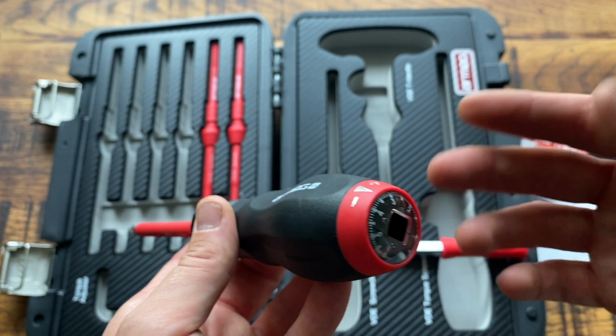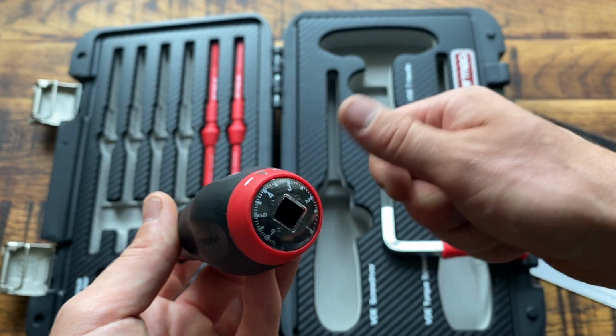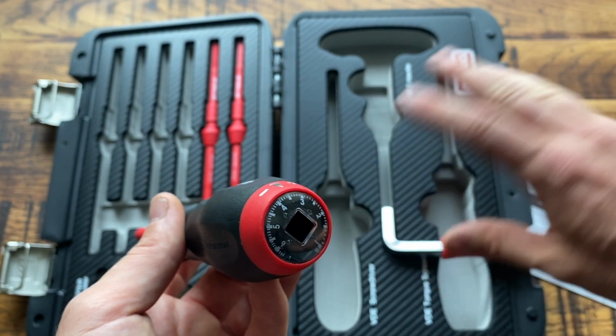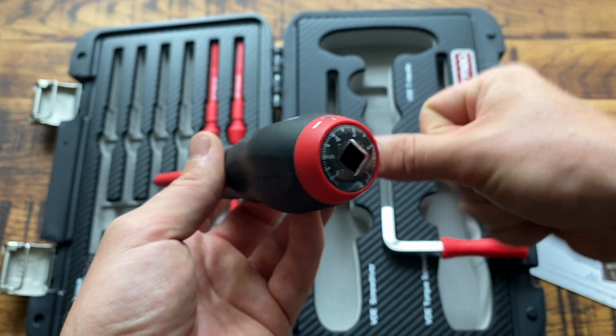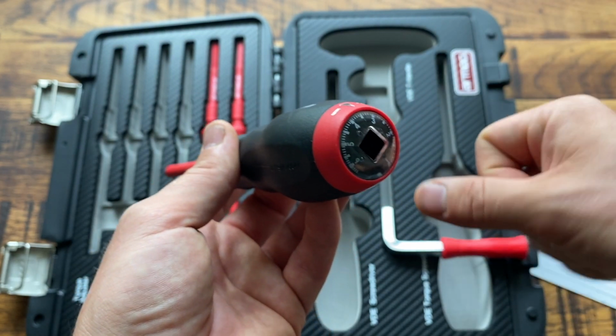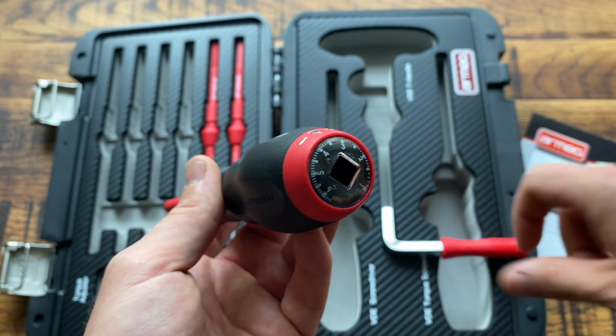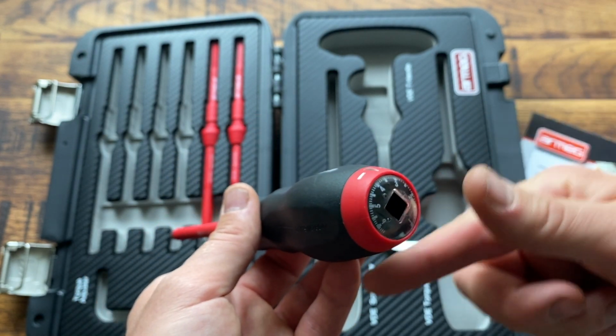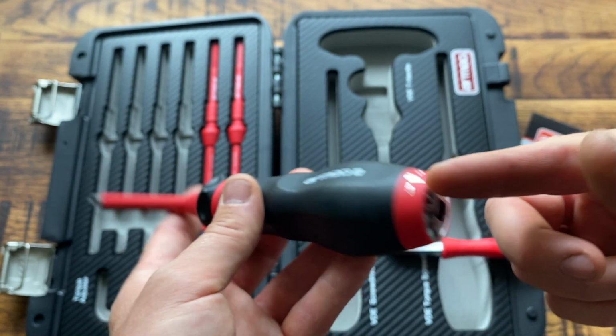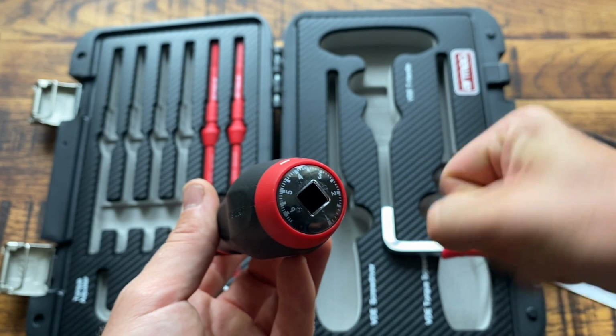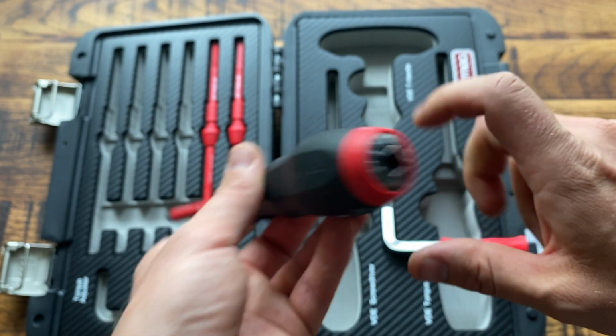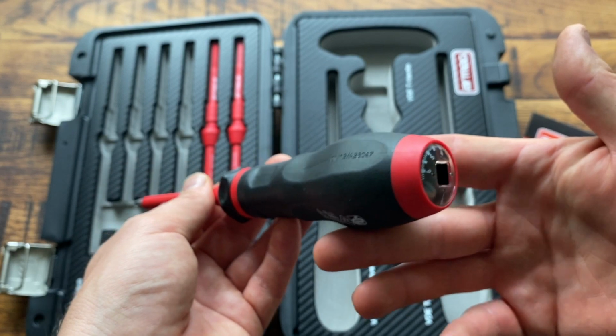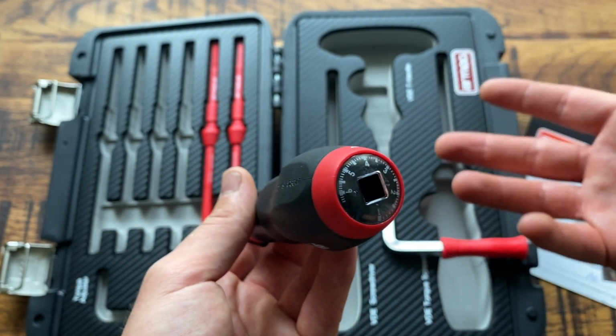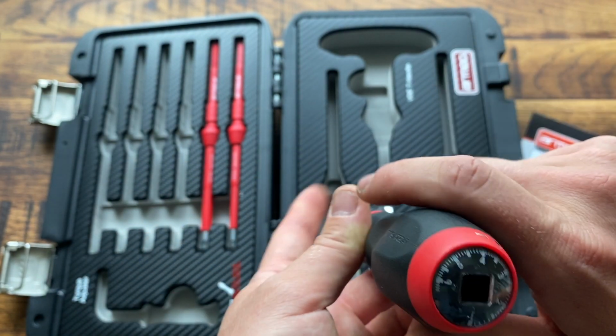A little mistake I was making is I was going with a manual screwdriver, tightening up all my screws in the consumer unit, and then just doing the final click on all the torque with the torque screwdriver. But actually you should do all the tightening with this, because you could have over tightened it with your normal screwdriver, and then this will click, but that doesn't mean you're not over the correct torque setting. So you have to be careful about that.